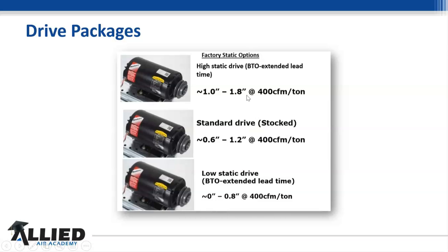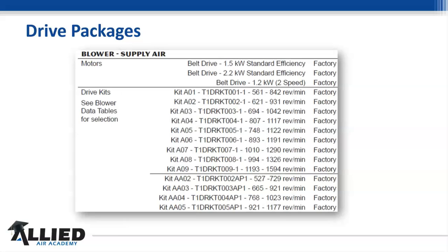So it's really important to know what standard, low static, and high static drives are. Usually high static drives are built to order. Those are usually plan and spec, or they're going back into a market where there was another specific brand put on there that had high CFMs. And the reason this is important, if you look, and I pulled this out of the spec sheets, a lot of people go, man, that thing's got over 9 different drive kits in it. And then for special occasions, you've got different drive kits above and beyond that. That's why it's important to know your statics, and we'll go over all that.